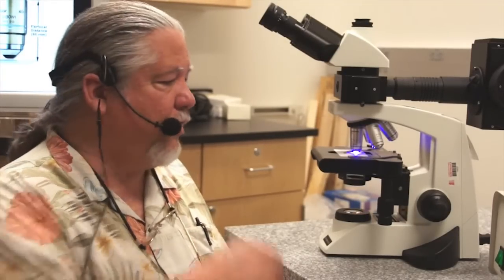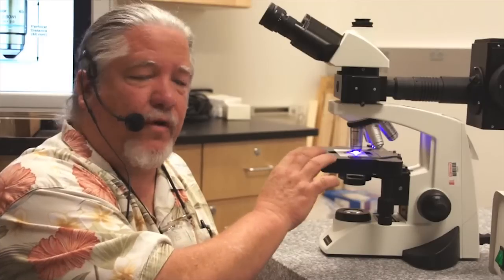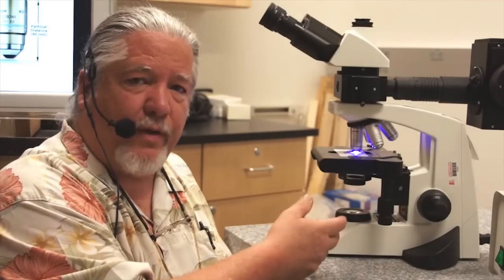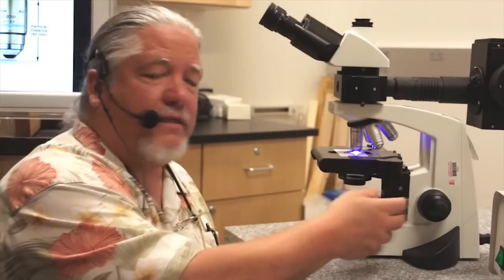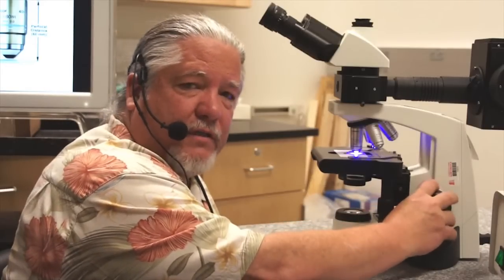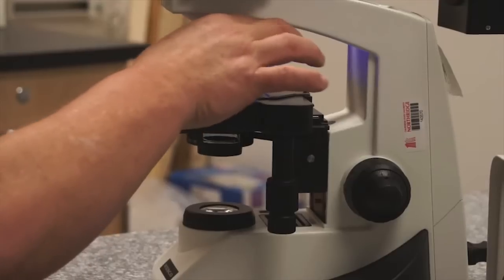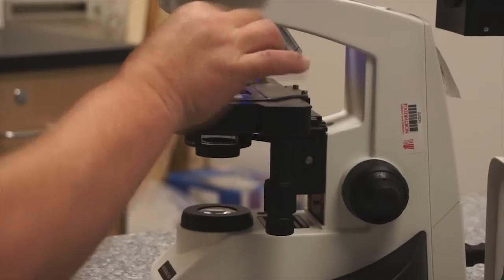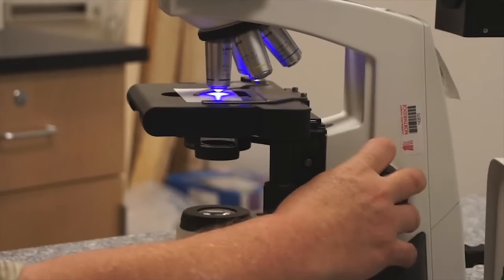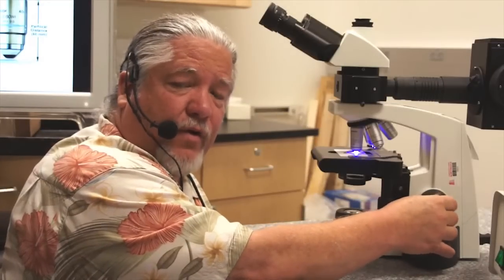Another important concept on the microscope is the concept of parfocality. When you're looking through a 10x objective and you're in focus and you want to go to another magnification, it's not necessary to lower the focus of the stage. You can be in focus at 10x and go to your 20x or 40x and be within half a turn of the fine focus. This is called parfocality and is available on most modern microscopes.